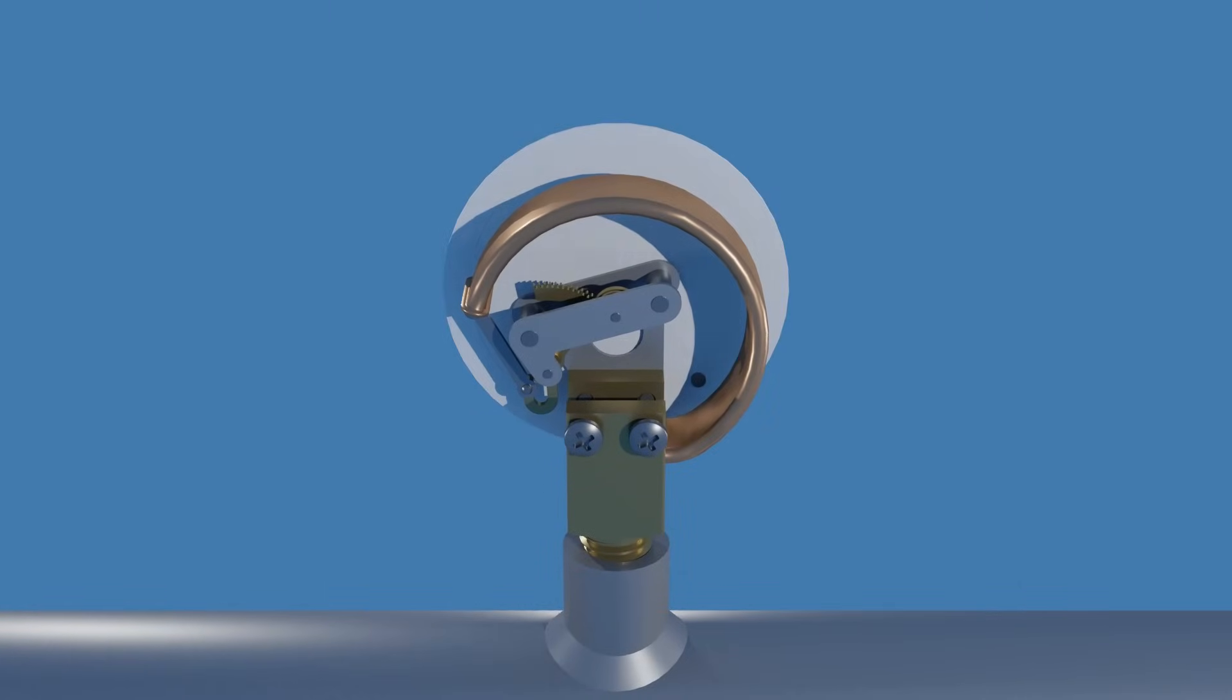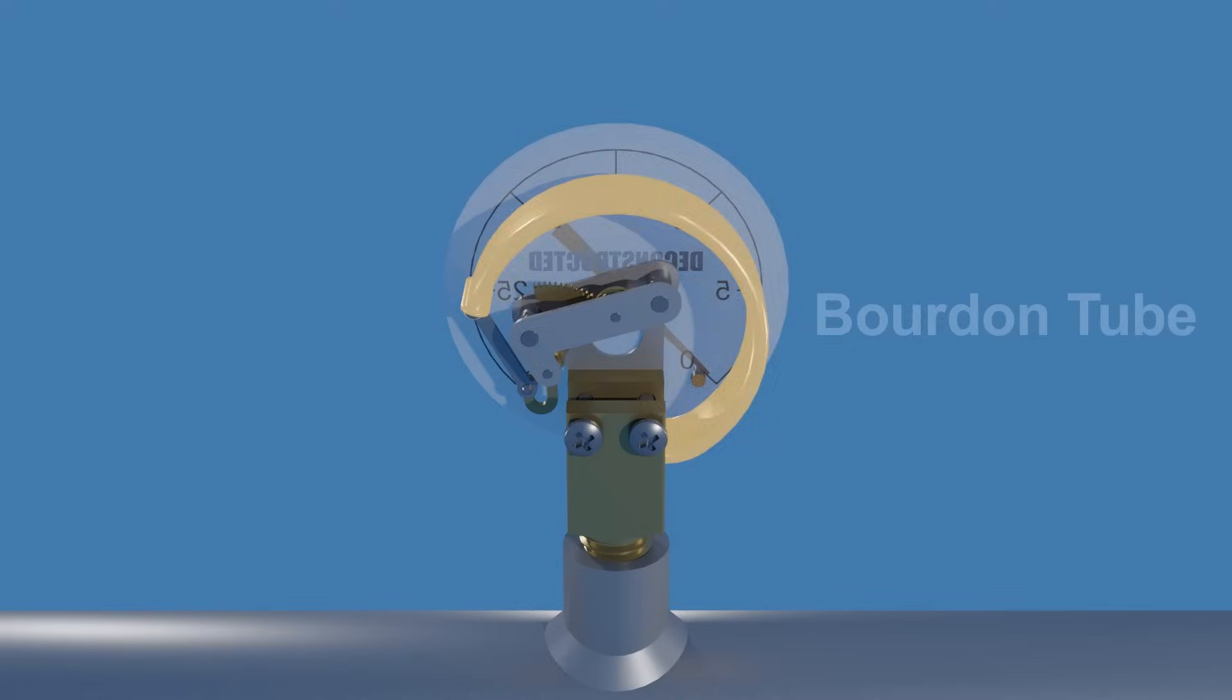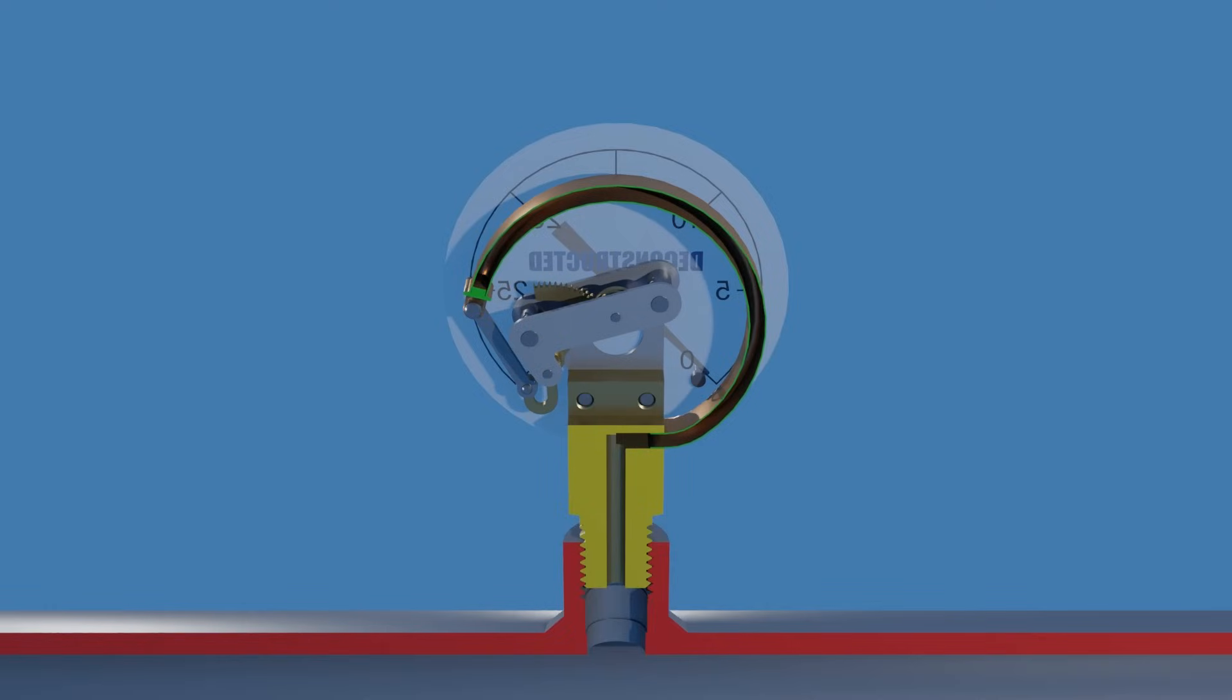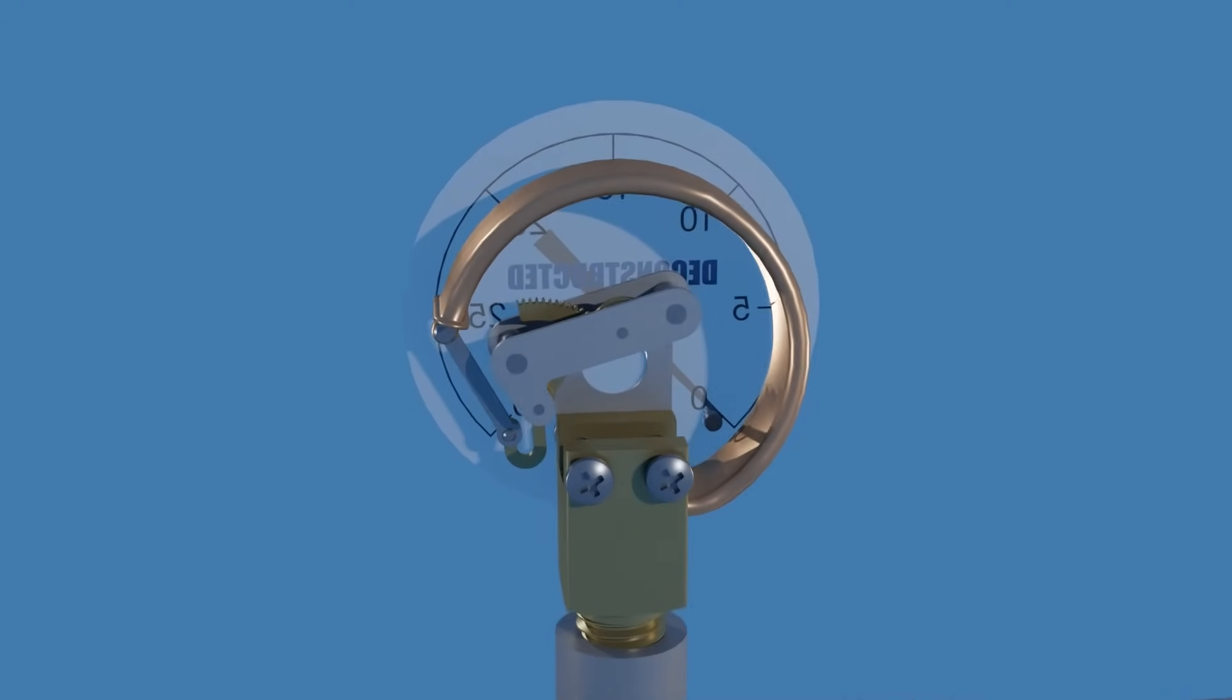Now let's look at the mechanism inside the pressure gauge. This is the pressure sensing element called a Bourdon tube. It's a C-shaped thin-walled metallic tube with an oval cross section. Its working principle is based on the elastic deformation of a curved, flattened tube when subjected to pressure. The tube deformation is proportional to the applied pressure.